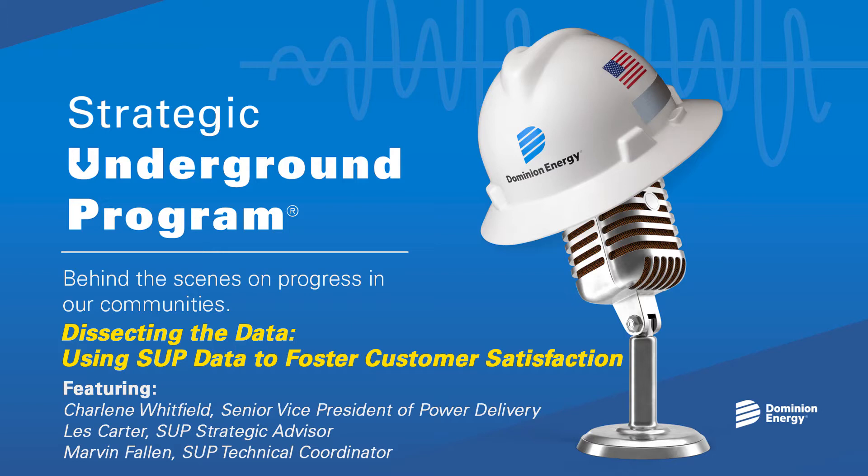First, it's important to understand this is a data-driven process. We look at all the tap lines in Virginia with protective zones more than 400 feet in length that experience two or more outage events over a 10-year period. These are mostly single-phase taps, but we do convert some multi-phase taps, provided they only serve single-phase load. Then we calculate an events per mile score for each tap line, and if that number is high enough, the tap becomes what we call a candidate for conversion. We have a database of about 4,000 miles, including taps that have been converted, some that are in process, and others we haven't yet reviewed. Occasionally, we do add a non-candidate tap line if it relates to other candidate taps.